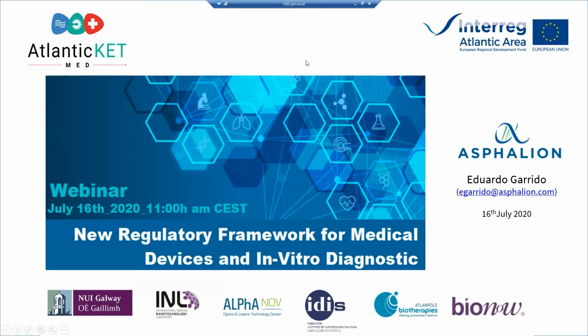In these reports, you will assess the performance of your device. It's important to demonstrate that your device provides more benefits than the risks it implies. So before certification, yes, you will have to provide evidence of both safety and performance, not just safety. It's necessary to give information about how well your device is performing. It's not just about whether it's safe or not. Obviously it has to be safe, but it has to be effective as well. It has to be doing something. So you have to demonstrate this. It's not something you can just postpone until post-market. You have to do it before you send the documentation.